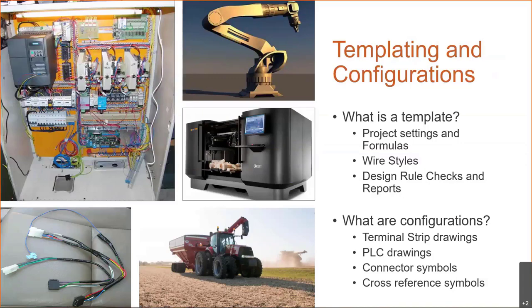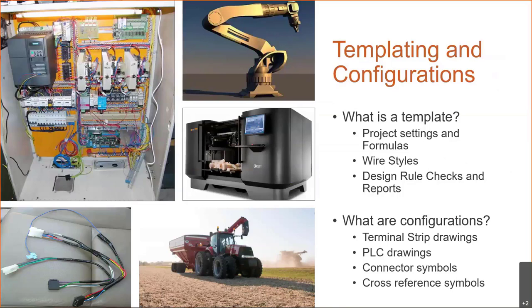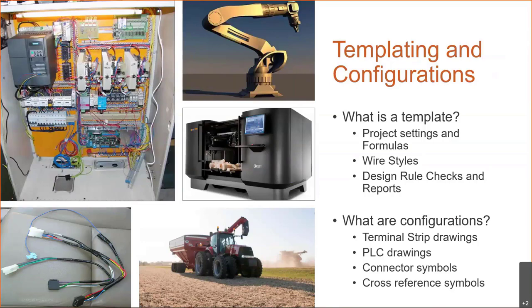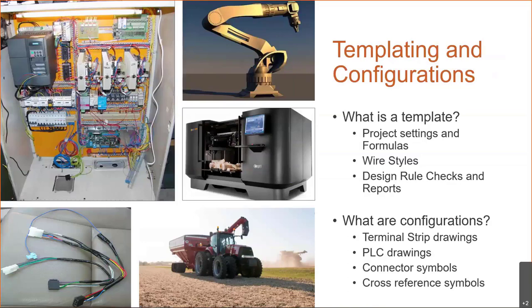And what are configurations? Well, configurations are rules for generated content. So instead of you creating a terminal strip drawing, you can create the rules and it'll generate that terminal strip from your schematic. You plop some terminal symbols on your schematic. You say, draw a terminal strip, and it'll look at those rules and apply that for you. Same thing can be true for things like PLC drawings for connector symbols, cross references. I'm going to mention PLCs real quick here as well because, you know, yes, I have all these inputs and outputs. Great. Well, that PLC configurator is going to handle more than the PLC symbol. It's going to also handle the circuit, the items that are attached to each channel. And we'll see that here in a bit.